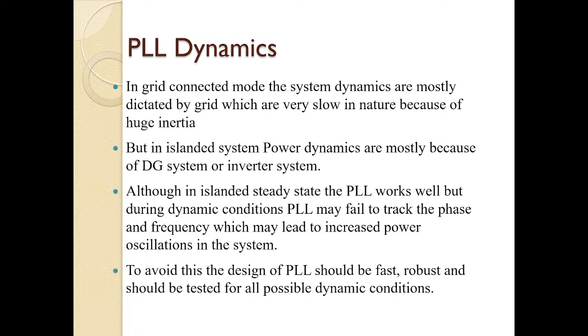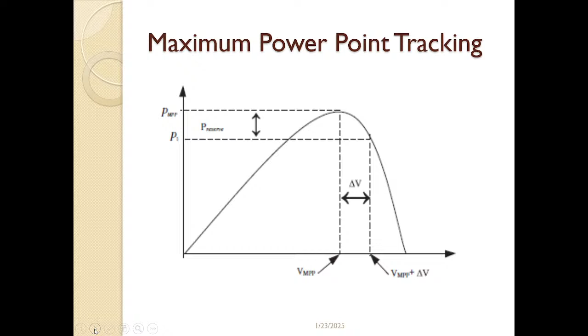So as I have told you, there will be an MPPT point and there will be a flexible MPPT point. So you can see here, the peak is your MPPT point and the P1, which is the less MPPT, is your flexible MPPT point. So by adding a delta V to the DC voltage control equations and the reference value of the DC voltage control loop, you will be able to operate the power at any desired point. And that is called the flexible MPPT mode of operation. Next.